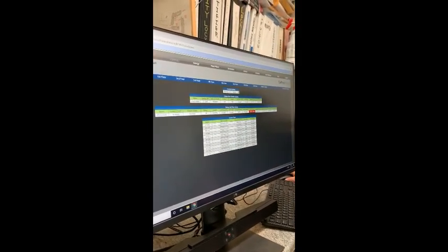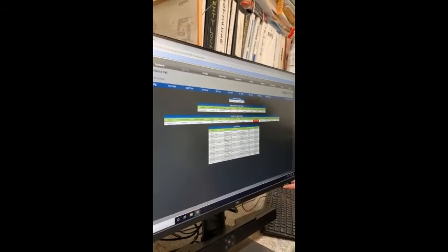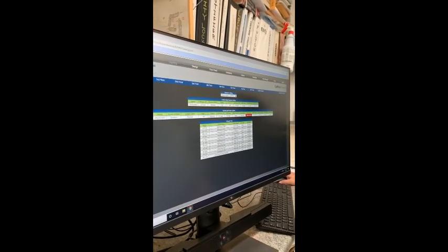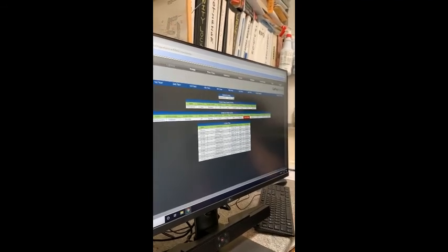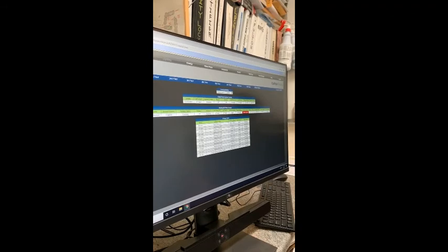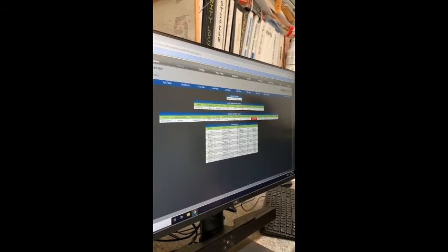There's nothing we would actually do at those JACEs, right? Like the metering ones? Yeah, it's more for, if we lost control to all of one floor, then at least we would know where it is. We could go look and see if there are lights on it, see what it's doing, or half of the time you unplug it and plug it back in to try to get it to reset. And see if the network lights are on or off on it. But you rarely do that, you haven't done it now, right? No, we've never had a problem.